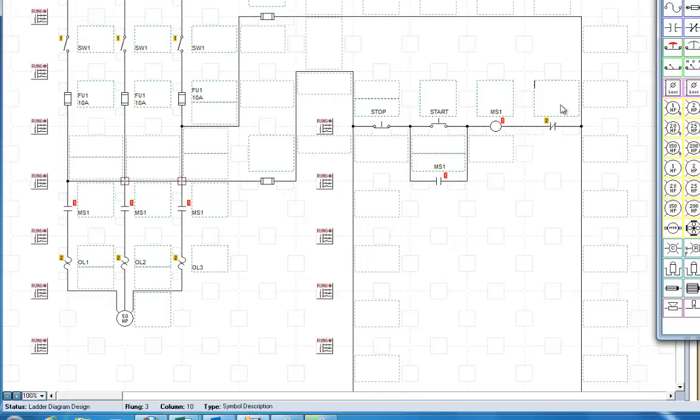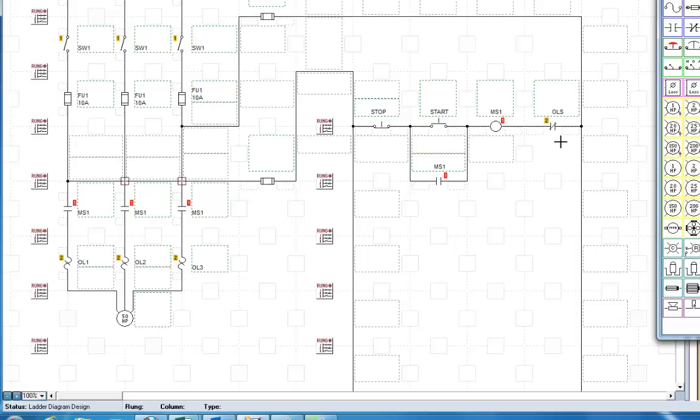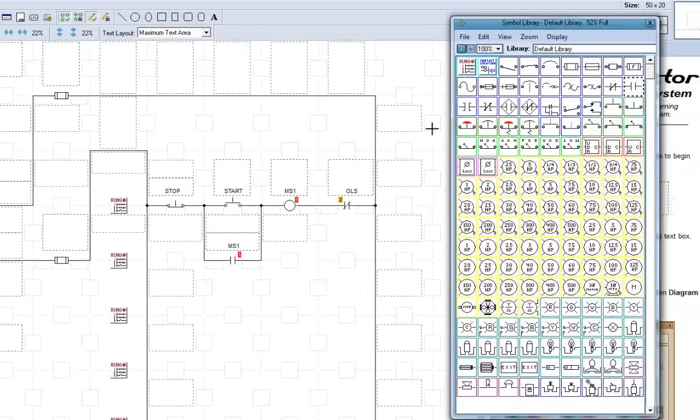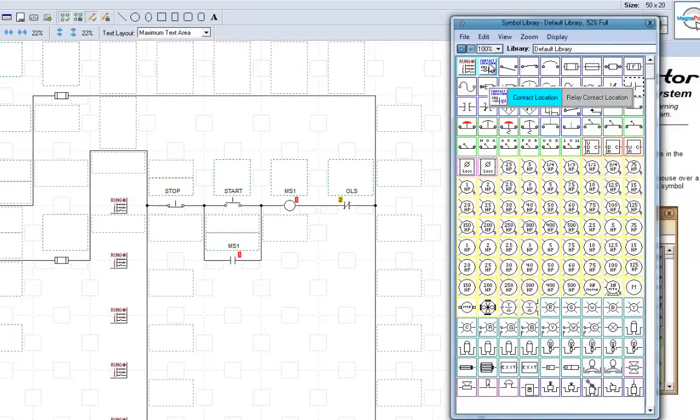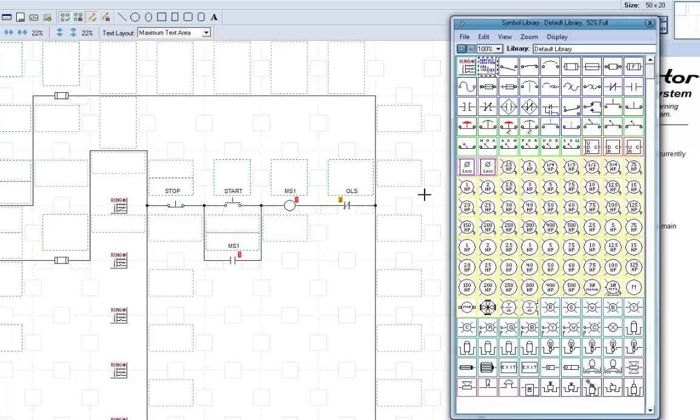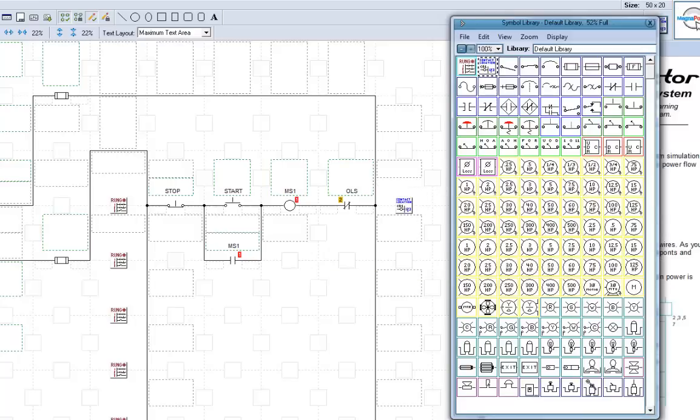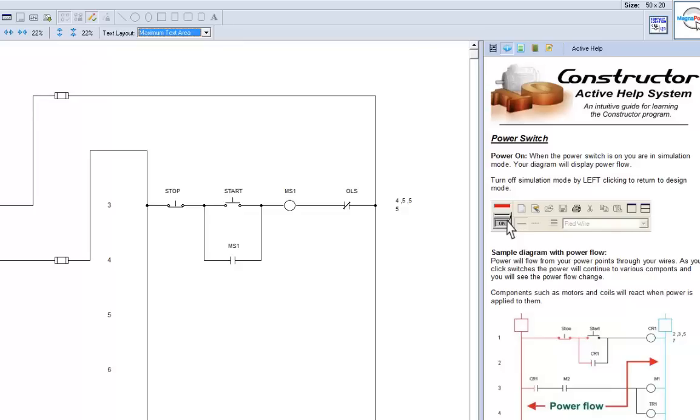This is our basic diagram. And there's one more thing to add. And that's the coil cross reference. That's this symbol right here. Give you a relay contact location. We'll click that. Now, what that will do, we turn this on. It tells us that we have normally open contacts on 4, 5, 5, and 5.